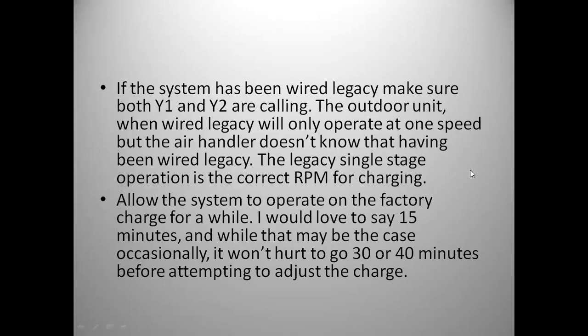Now, if by chance you're using thermostats like the Nests and the Ecobees and Honeywell 8000s, whatever people prefer, you can wire these legacy, which does kind of reduce your troubleshooting, because you're now relying just on the boards and not on the EcoNet to tell you specifically what's wrong with it. But if the system is wired legacy, you have to ensure that both Y1 and Y2 are calling. Verify they're engaged, and then your circuit board will also tell you, based upon capital C or lowercase c, if it's indeed in second stage. You're unable to verify what RPM you're in because you don't have the EcoNet, but you can still run.